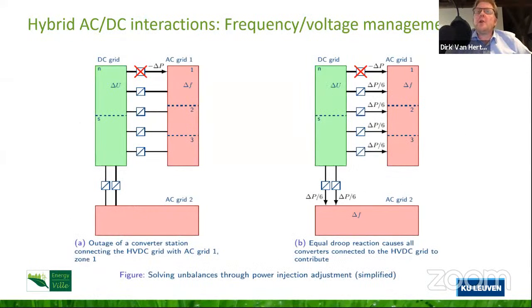We also need to think about how we manage our system. Here I have several small graphs showing how such a DC grid connected to two AC systems would work. You could imagine AC grid 2 is, for instance, the Dogger Bank offshore wind farm, and AC grid 1 could be continental Europe or the UK, with the DC grid in between. Let's say one of the converters goes out in the top left. What happens is that all the other converters take over. That means you have a frequency event in the AC grid and a voltage event in the DC grid, but also in the second AC grid you see a frequency deviation.